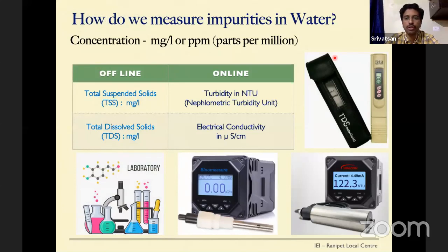The next question is, how do we measure these impurities? We have said that we have to measure the concentration of impurities in water. There are two methods available: one is offline, the other is online. Offline, we measure the suspended solids as total suspended solids in milligrams per liter. This is typically done in a laboratory. We take a filter paper, measure its dry weight, then pass a known quantity of water through it, dry the paper, and weigh it again. The difference in weight gives you the total suspended solids in the water.